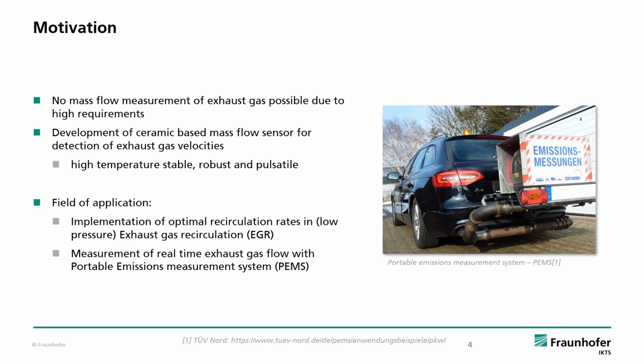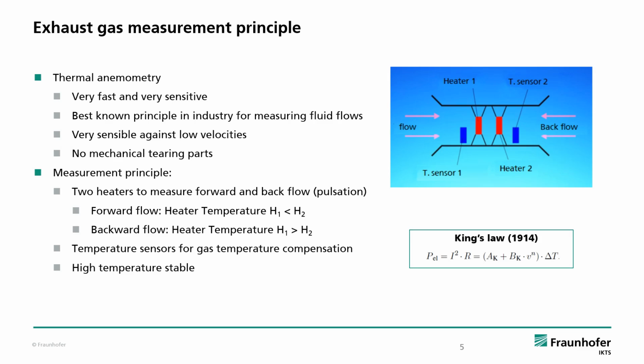Let's have a look at the principle. The measurement is based on thermal anemometry, which is very fast and sensitive. Besides, it is the best known principle in industry for measuring fluid flows and has no mechanical wearing parts. The picture shows a schematic of the principle adapted to detect pulsations.